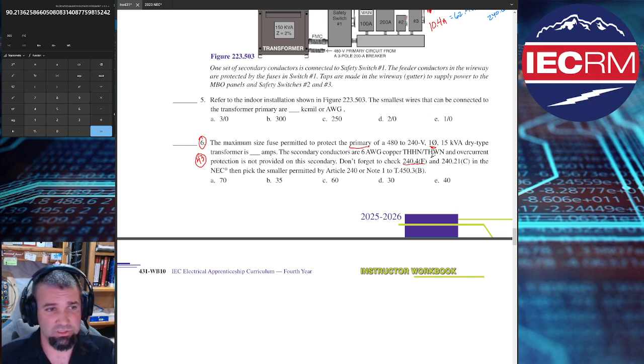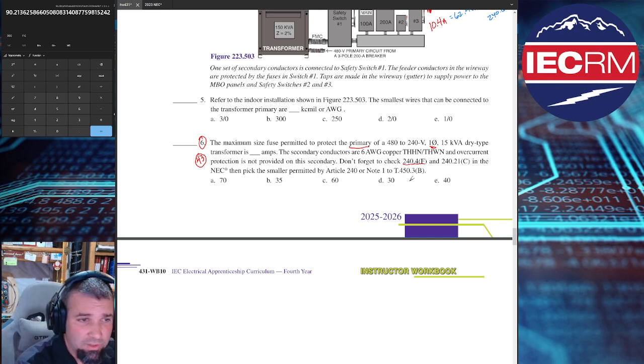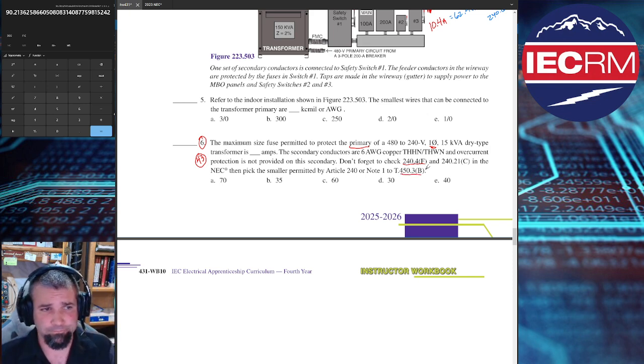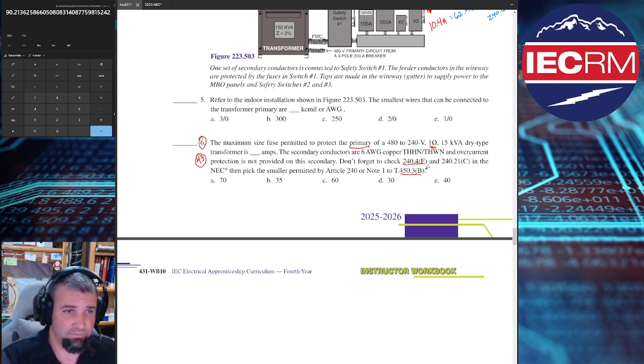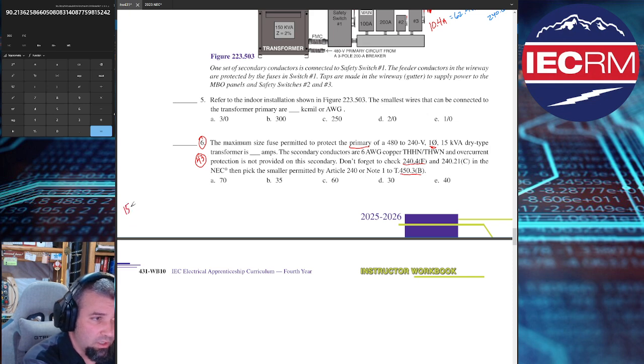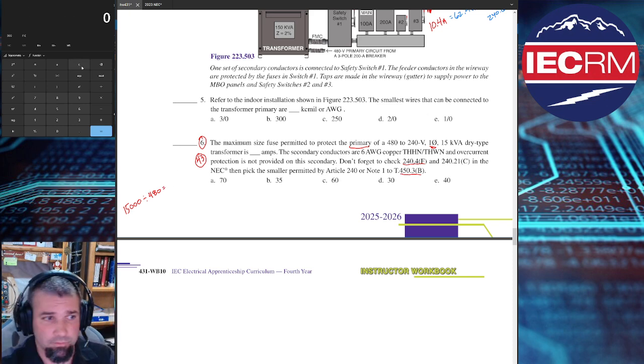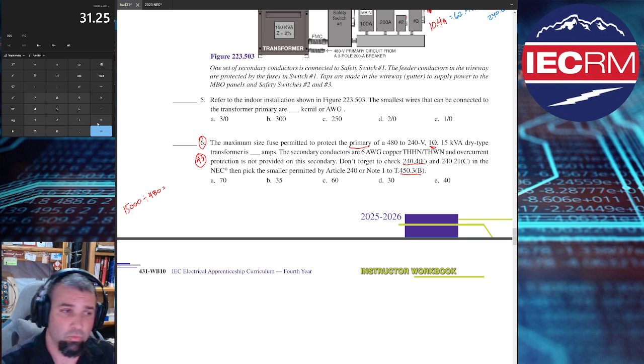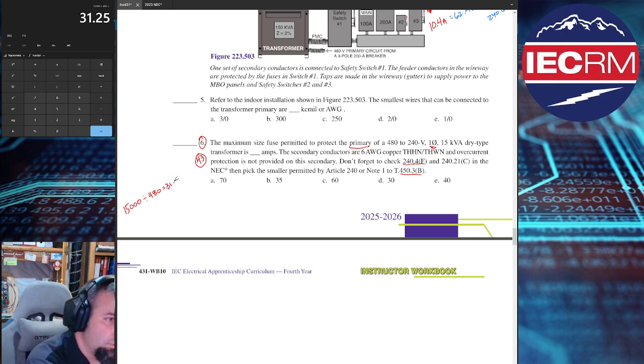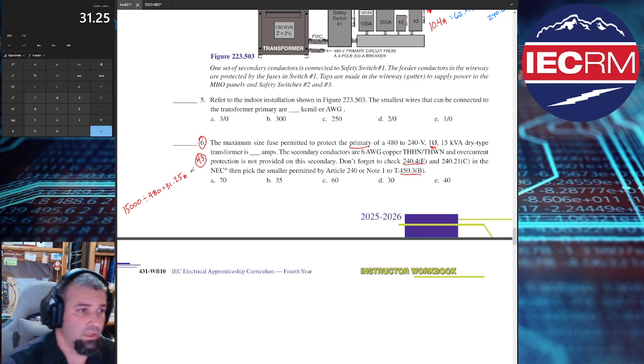Okay, so first, let's go ahead and size the primary right out of 450.3B since we're there and we've been used to doing it. Okay, so I have a 480 volt single phase 15 kVA transformer, so this is pretty straightforward. I'm going to do 15,000, right? 15 kVA, and I'm just simply going to divide that by 480. No 1.732 because we are in single phase here. Okay, 15,000 divided by 480 equals 31.25 amps.